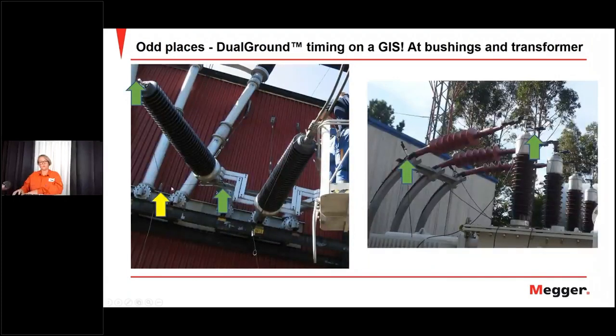Here is where we measured on our circuit breaker, which had these big bushings through the wall. And we measure at one side, which is grounded, and to the ground in the mechanism here, or sorry, in the structure here. And here we measure directly at the transformer. We connect up here at the transformer flag and on the groundings.